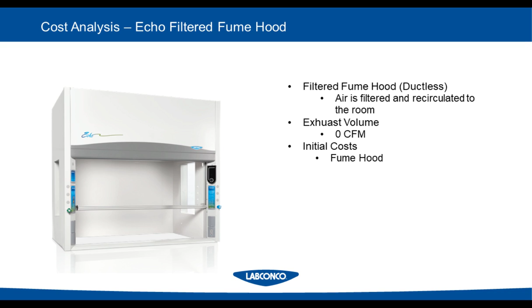And last, we're going to look at the Echo filtered fume hood. This is a ductless fume hood that we've sort of discussed. And in these hoods, air is filtered and then it's recirculated into the room. This means that the exhaust volume is 0 CFM. The initial costs are very similar in that you do need the fume hood, but where these hoods differ is that you need to order the filters that go with the fume hood. They are a separate cost.